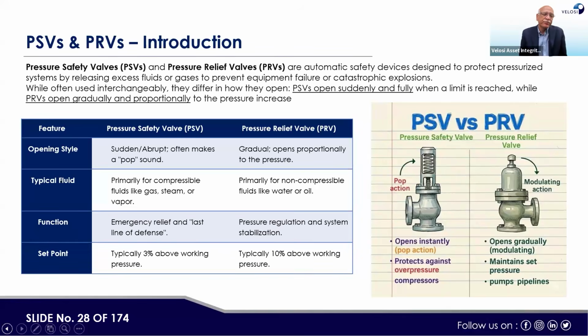So here, if we see, a pressure safety valve is basically required for gases, steam or vapors, whereas a pressure relief valve is normally for liquid service or water. Both PSVs and PRVs are installed for the protection of high pressure, medium pressure or low pressure equipment. If system pressure increases more than the design limit of that particular equipment, rather than the equipment bursting, the PSV should pop up. That is the purpose of the PSVs.